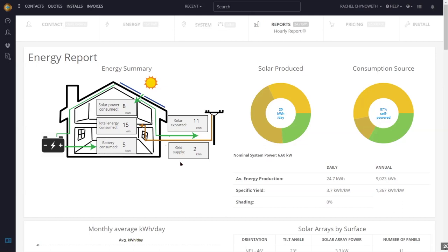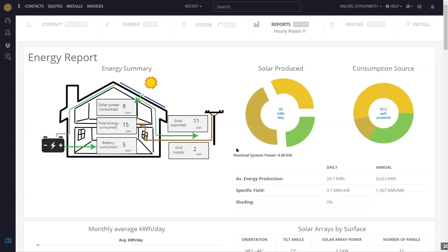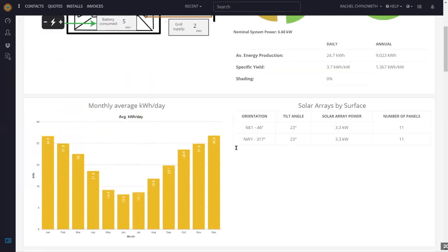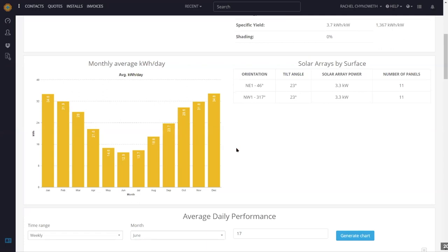Solar Plus produces a range of fantastic graphics. There's a house diagram that shows you the division of energy flow based on this system design. Total energy consumption was 15 kilowatt hours per day. On a daily average throughout the year, the grid supply will be 2 kilowatt hours, with the rest supplied by solar — 8 kilowatt hours — and battery — 5 kilowatt hours. We also have average daily energy production based on a year: 32% going to loads from solar, 24% going to battery, and 44% exported. We have monthly averages too, as it's not the same all year — this is based on an address in Victoria.